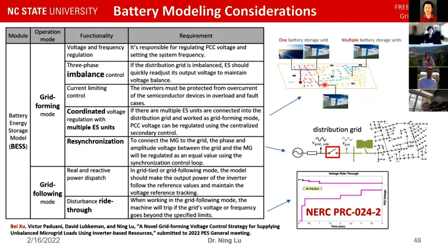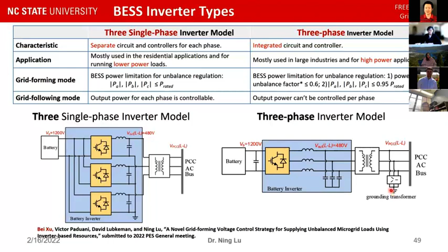To remove the imbalance, we're trying to see there are two approaches basically in the field. We can either use three single-phase inverters, which is very benign to this kind of unbalanced operation because you have three inverters to supply the load, or you have a three-phase inverter model. This is more prone to imbalance, and it heavily depends on whether or not you have a grounding transformer to actually mitigate the zero sequence current.